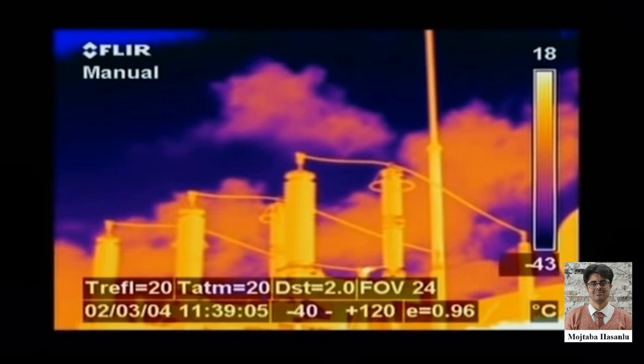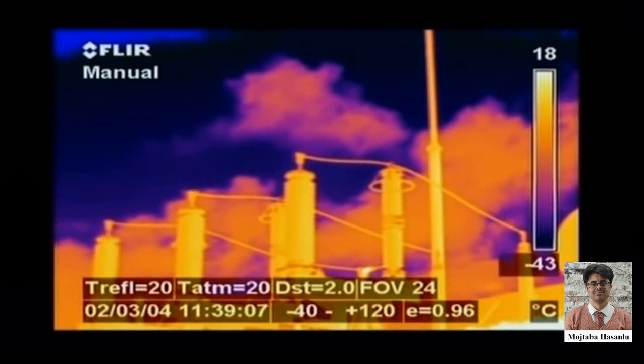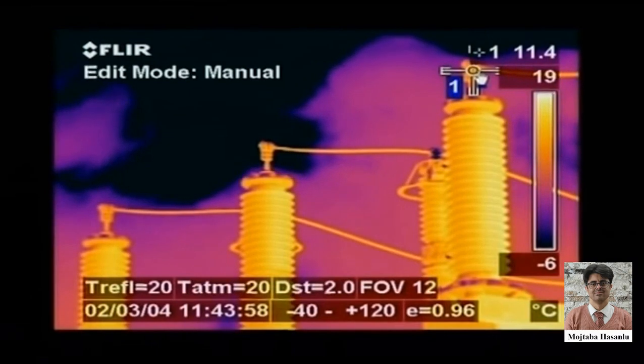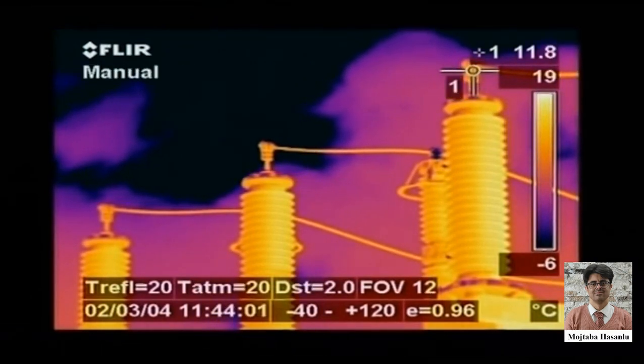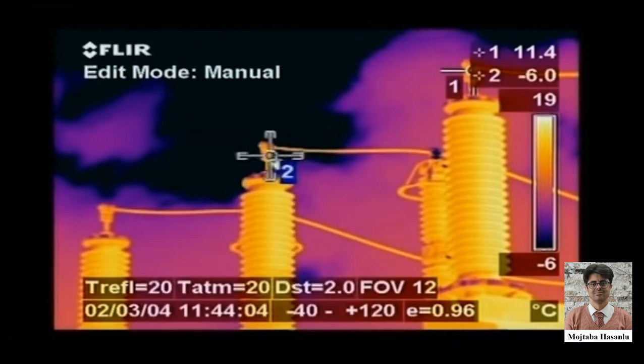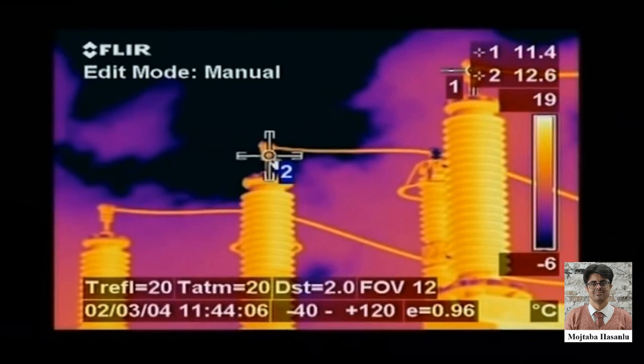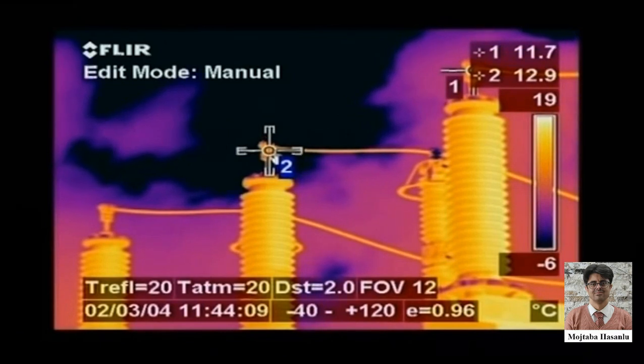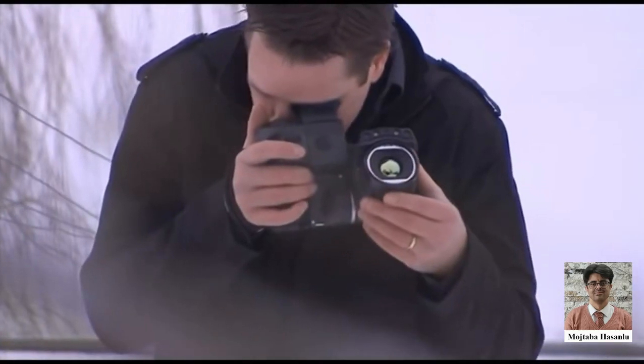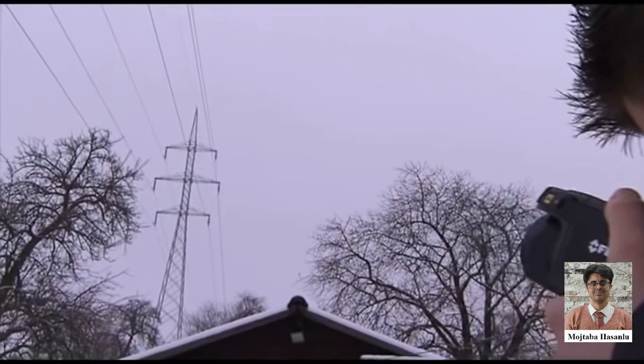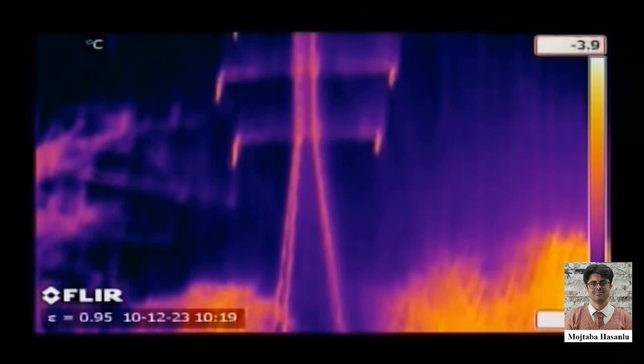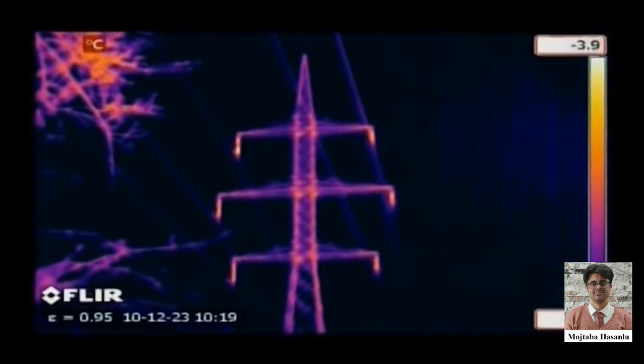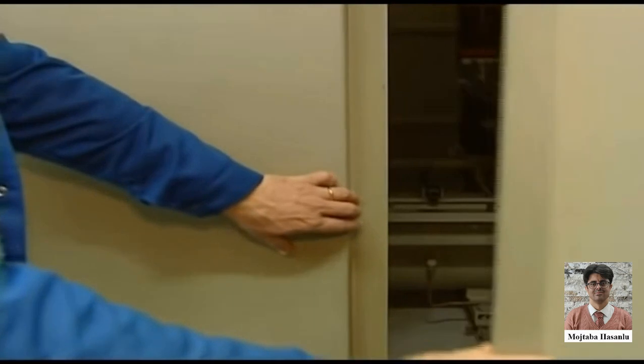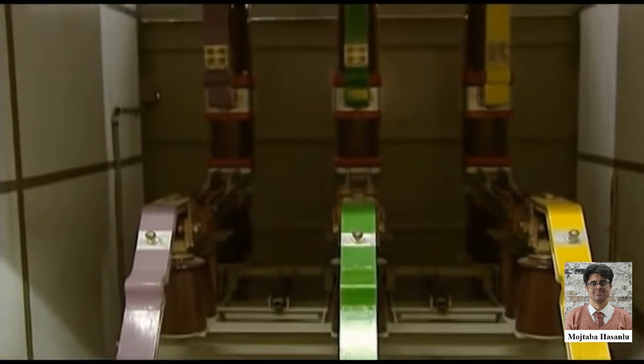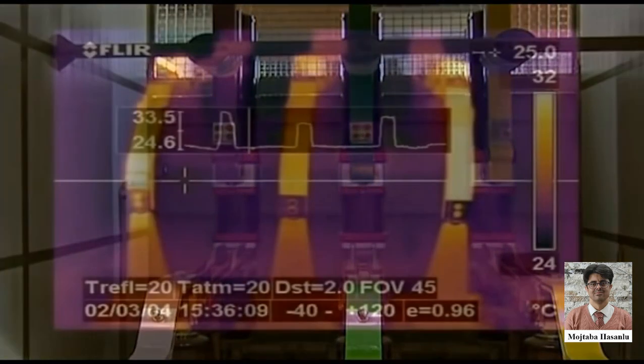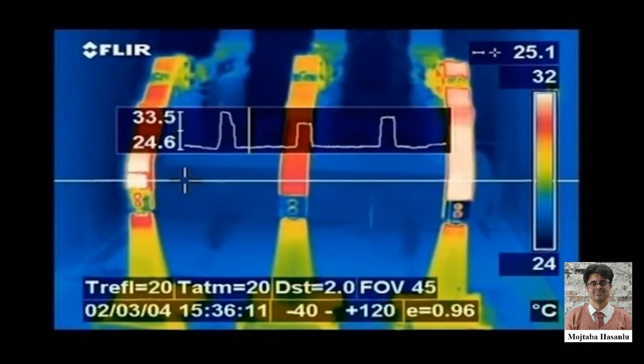Power transformers are often checked with thermal imaging cameras. Temperatures of the cooling fins and the high voltage connections can be compared so that if necessary, corrective action can be taken before real problems occur. Also, high voltage power lines can be inspected with a thermal imaging camera. Other high voltage installations that are checked with a thermal imaging camera include circuit breakers and switches. Potential problem areas will clearly be shown on the thermal image.